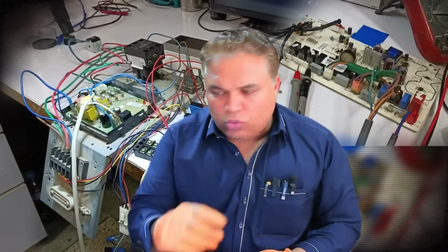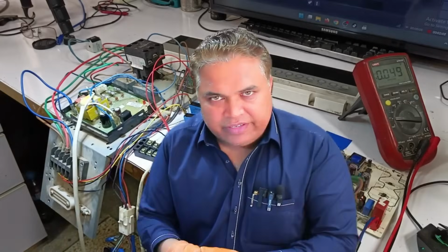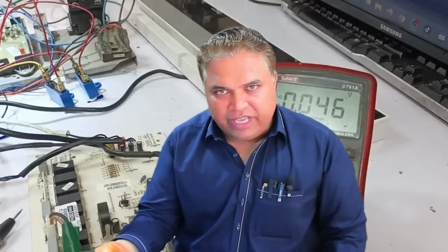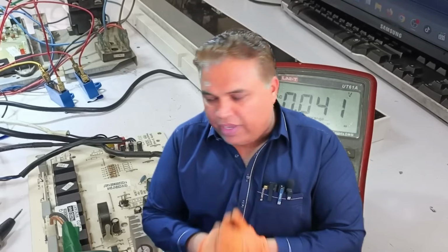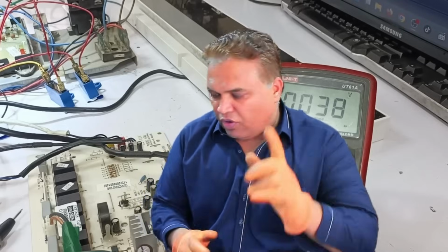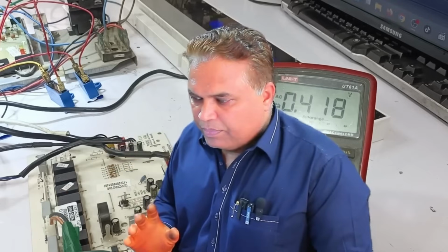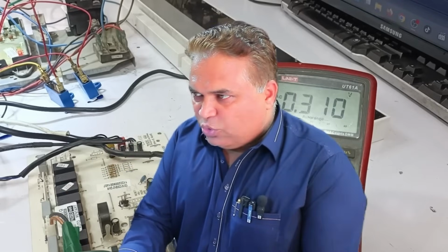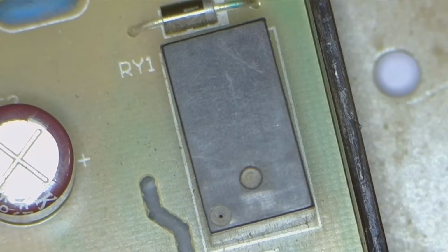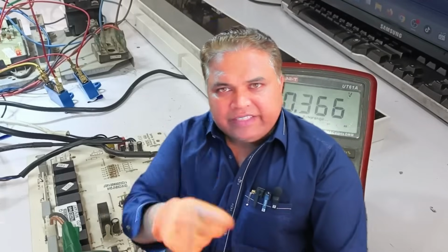Now all the required components between the indoor and outdoor units are complete, and the fake 3-phase supply has been generated. So let's now see what fault this PCB is creating. I am now connecting the power supply. I turned on the switch, and the unit powered up. The relay has also switched. When the RY1 relay switches, it means that the phases and the pressure switch are working perfectly fine. These are the only 2 controls managed by this PCB.